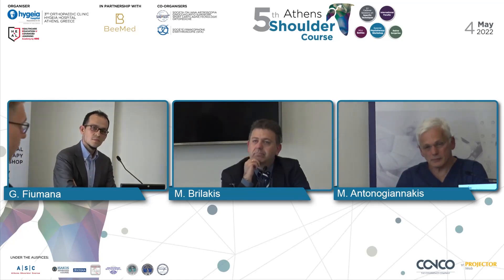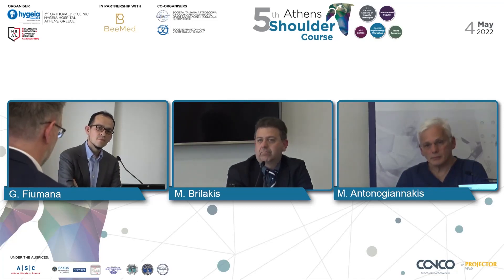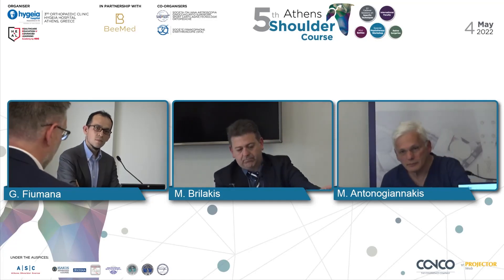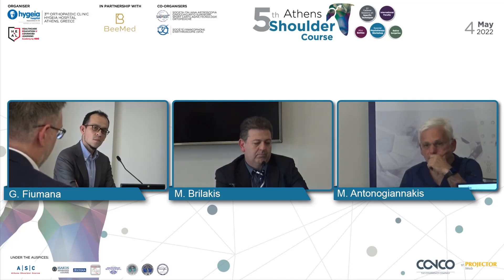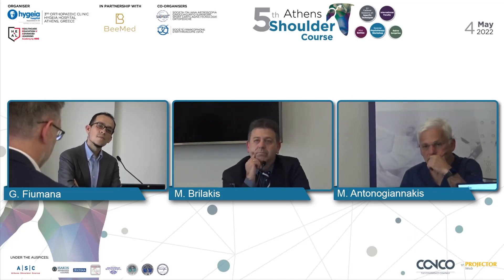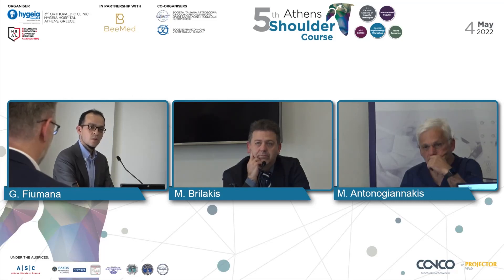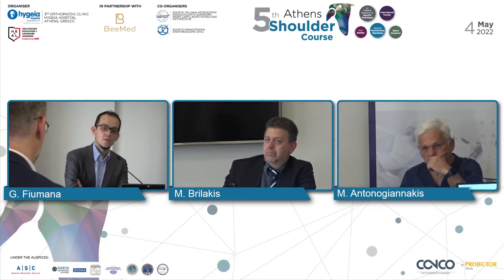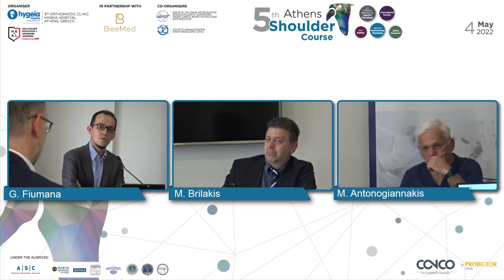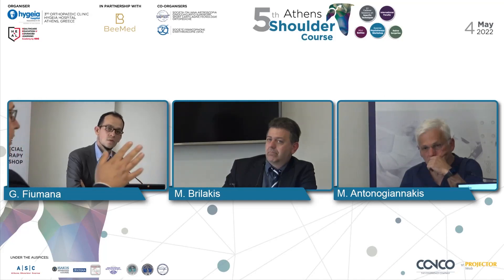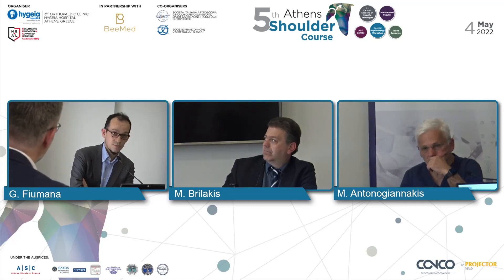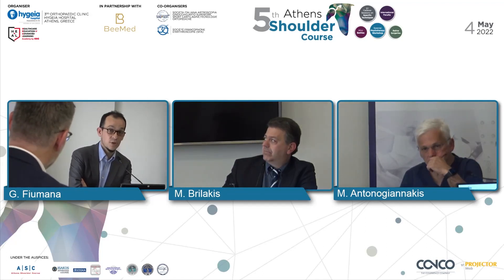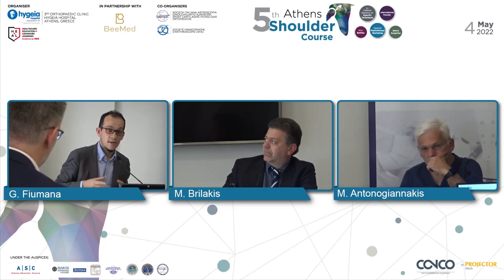From the Q&A on surface EMG: the main concern with any device using superficial pads is first, that placement must be very precise, and second, the noise from surrounding muscles — the crosstalk. If electrodes are placed on the infraspinatus, for example, nearby muscles interfere. The response: only superficial, large muscles are detected where crosstalk is minimal. Deep muscles like the subscapularis cannot be reliably detected with surface EMG.